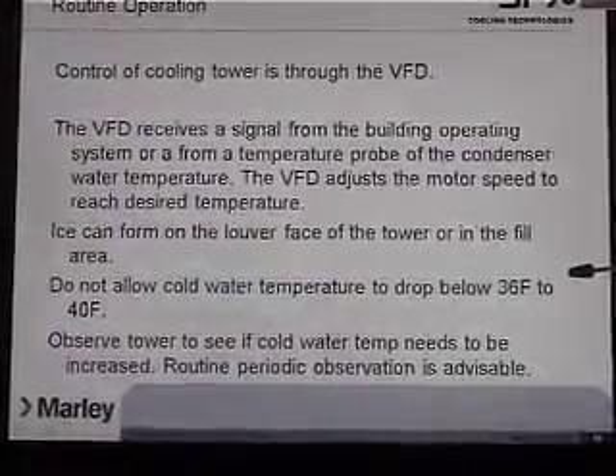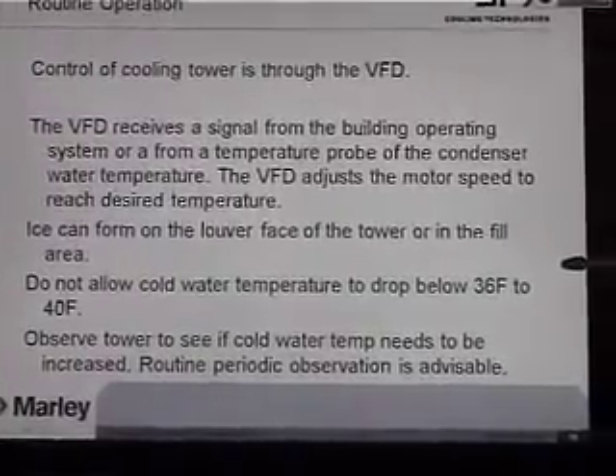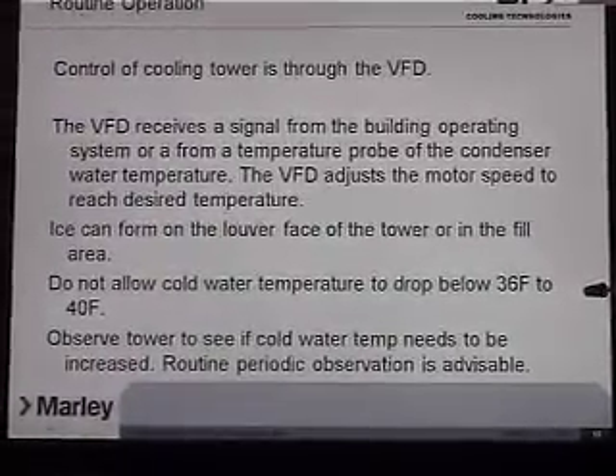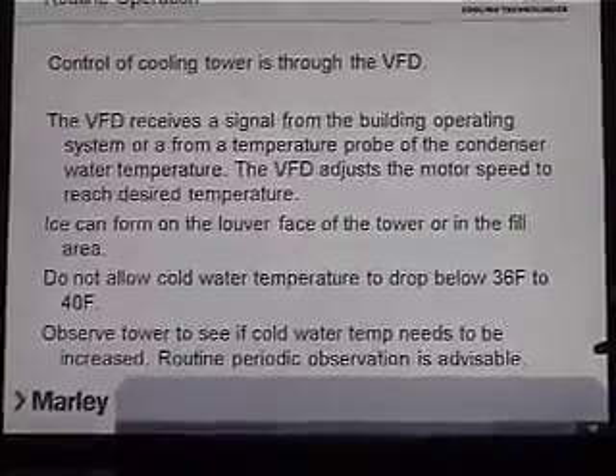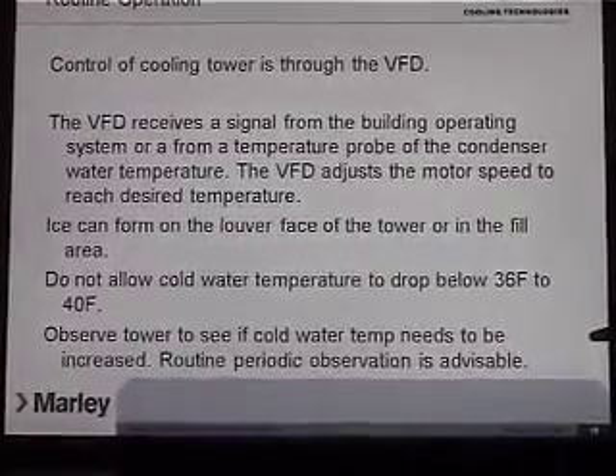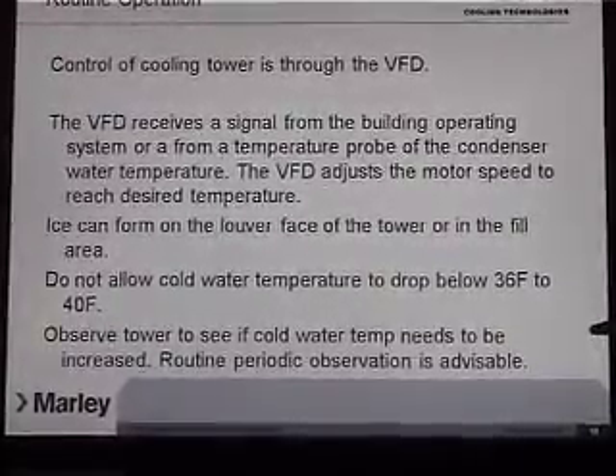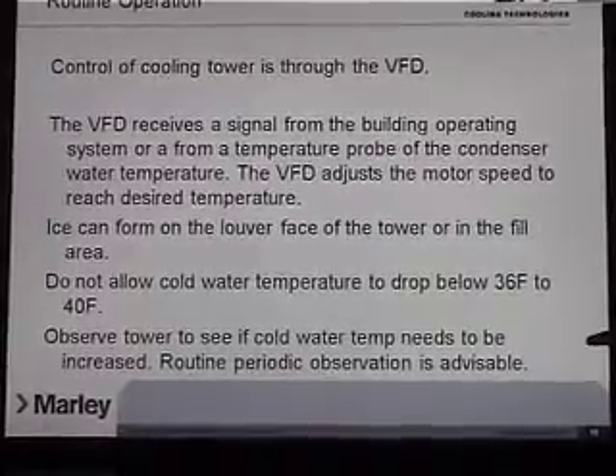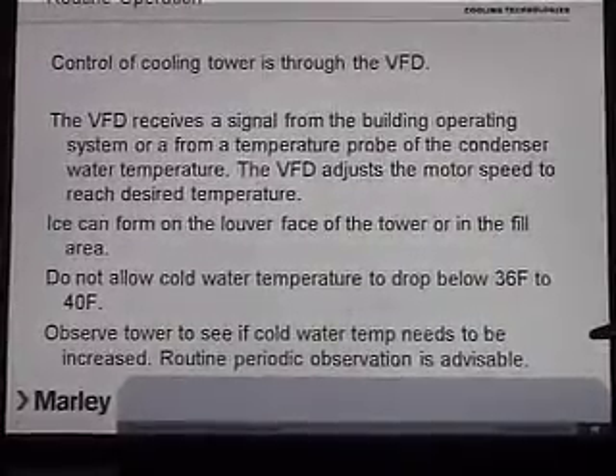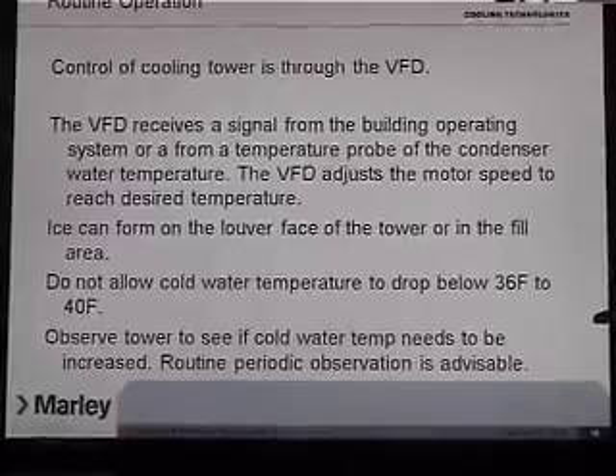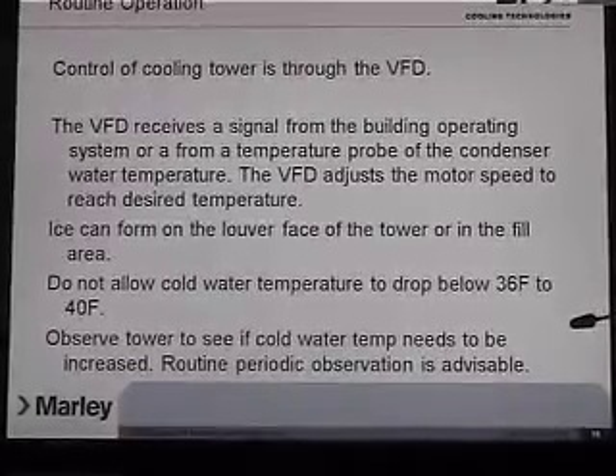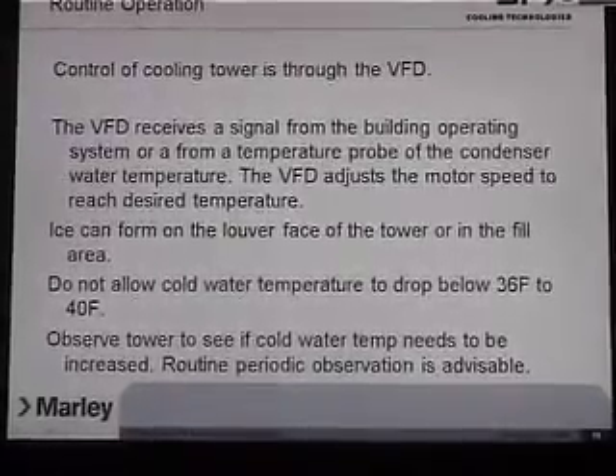You shouldn't allow your cooling tower cold water to drop below 36 to 40 degrees. And if you're running pretty cold water, you'd want to check in your louver face and your fill to make sure there's not an excess of ice forming.